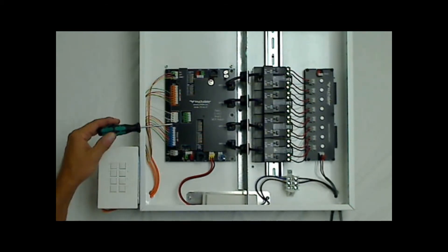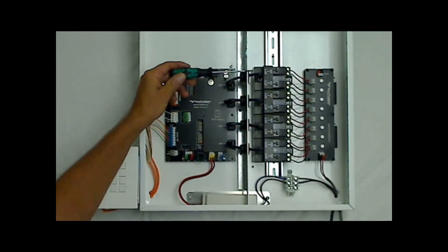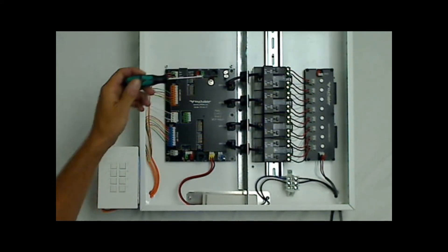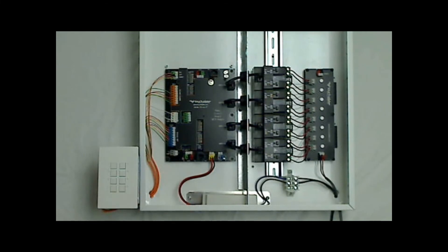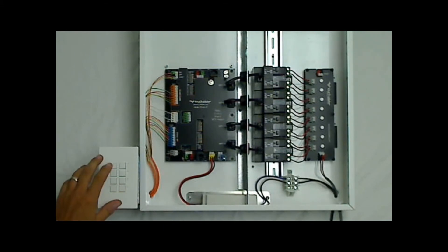The next set of dip switches is the options. In the options, number 7 will be the only one used. Number 7 reverses the order of the relays. The preset is relay number 1 being at the top. If number 7 is turned on, relay number 1 will now be at the bottom.